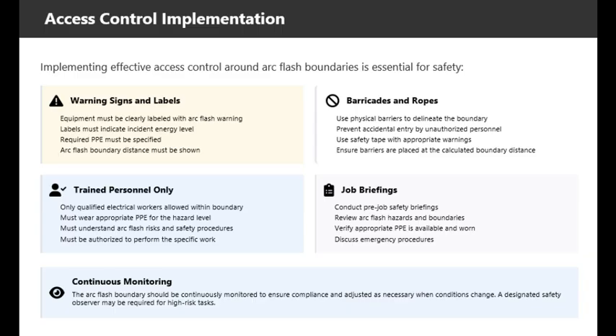Establishing the arc flash boundary is only the first step. Implementing effective access control is what actually protects workers. Let me walk you through the key components of effective access control. Warning signs and labels are your first line of defense. Equipment likely to cause an arc flash must be clearly labeled with arc flash warnings. These labels must indicate the incident energy level, specify the required PPE, and show the arc flash boundary distance.